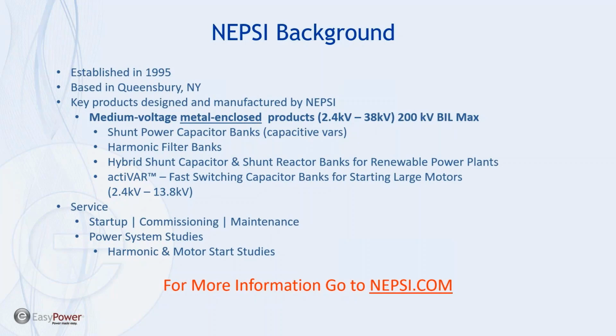In a typical instance nowadays, firms are using VFD drives and reduced voltage soft starts to start motors at the medium voltage level between, say, 1,000 horsepower all the way up to 25,000 horsepower. This fast switching capacitor bank is offered to support the reactive power requirements of those large motor starts at a fraction of the cost of a VFD drive, and also at a fraction of the complexity and the cost. So on to the presentation.